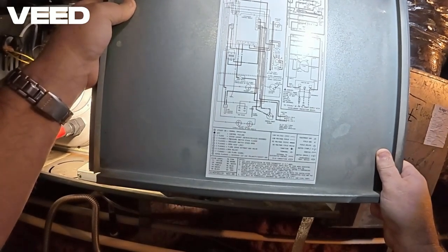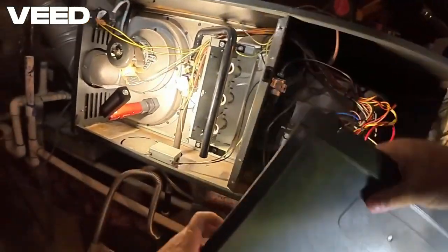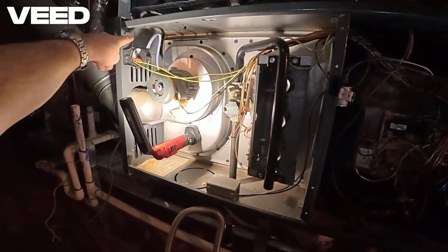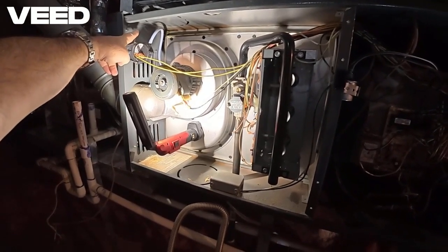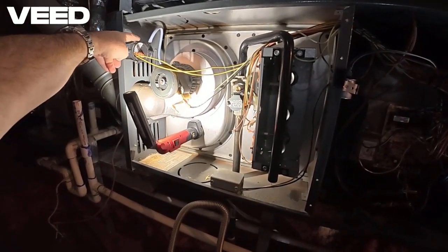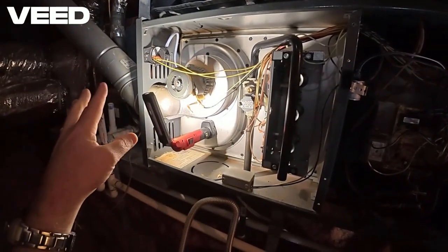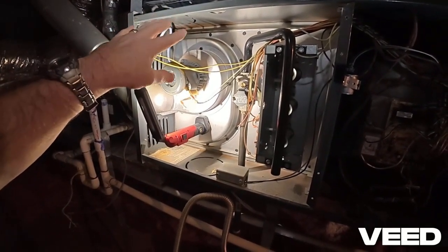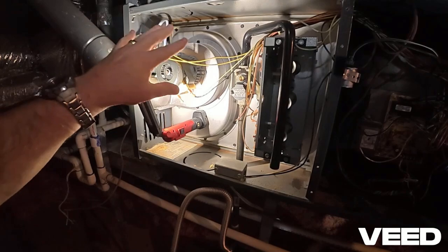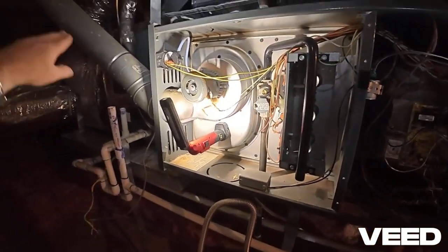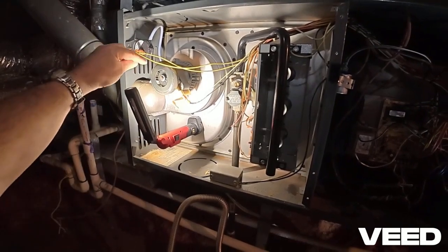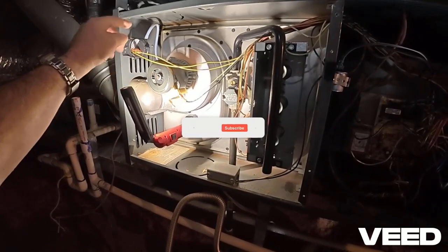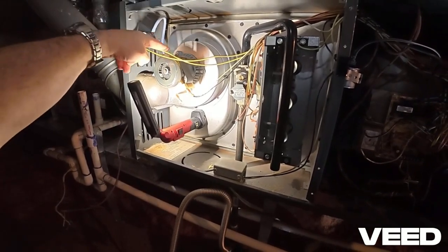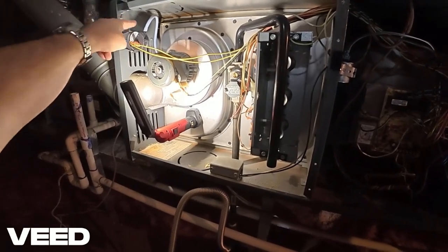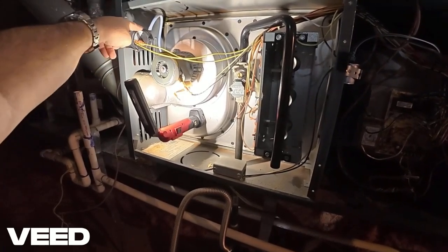2 flashes means the pressure switch is stuck closed. 3 is a pressure switch is stuck open. So let's look at the pressure switch. We've actually looked at a case of one of these a couple weeks ago, and it's on video, and it was stuck open. So these are typically open, and if you remember, the purpose of the inducer draft motor is to turn on and remove combustible gases from the heat exchanger and blow them out the flue pipe here. So in the sequence of operations, the inducer motor is first to turn on, and it's validated by this pressure switch. So the pressure switch is normally open, and it will close when it senses the draft. So there's a little rubber diaphragm in here, and it will close down when the motor is on.